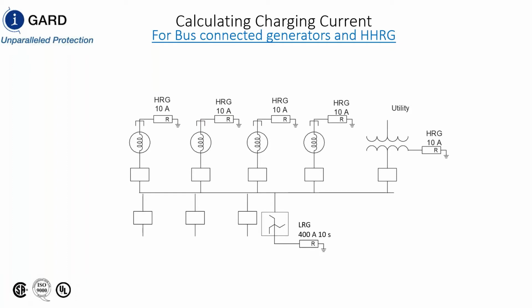Can you talk about the design of Zig Zag transformers for a split bus tiebreaker system? Well, if the tie is open, each half of the system will be its own source. If, however, the tie is closed, those two zigzag transformers and resistors will be in parallel.